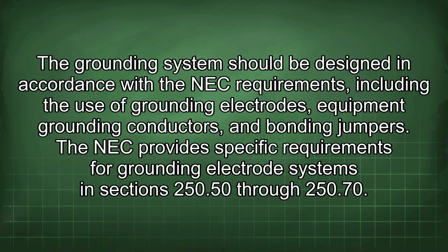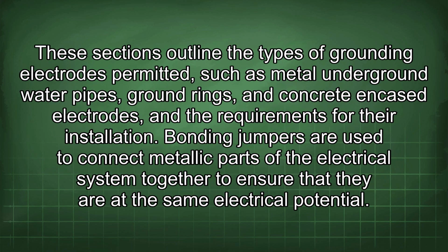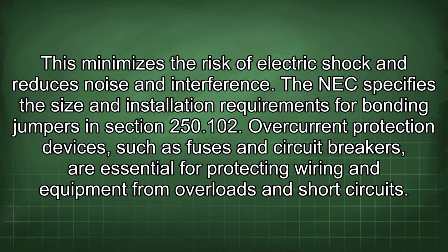The grounding system should be designed in accordance with the NEC requirements, including the use of grounding electrodes, equipment grounding conductors, and bonding jumpers. The NEC provides specific requirements for grounding electrode systems in sections 250.50 through 250.70. These sections outline the types of grounding electrodes permitted, such as metal underground water pipes, ground rings, and concrete encased electrodes, and the requirements for their installation. Bonding jumpers are used to connect metallic parts of the electrical system together to ensure that they are at the same electrical potential. This minimizes the risk of electric shock and reduces noise and interference. The NEC specifies the size and installation requirements for bonding jumpers in section 250.102.